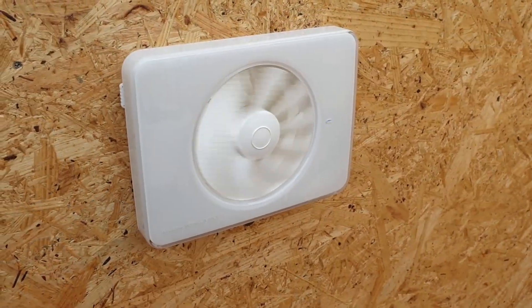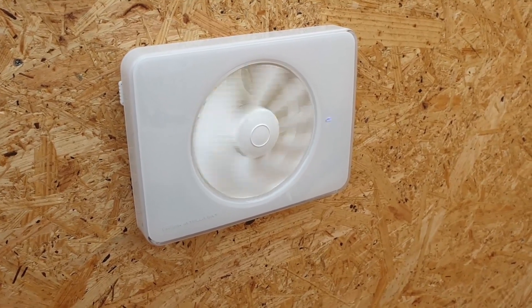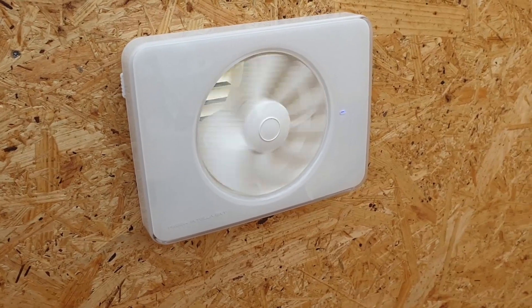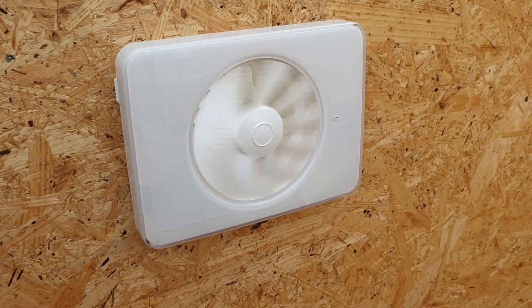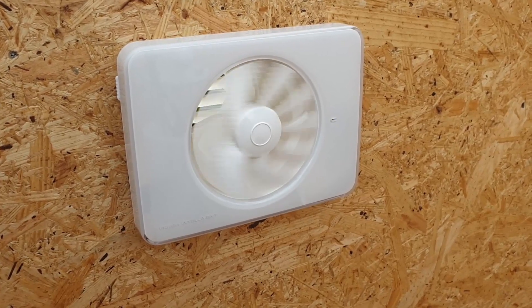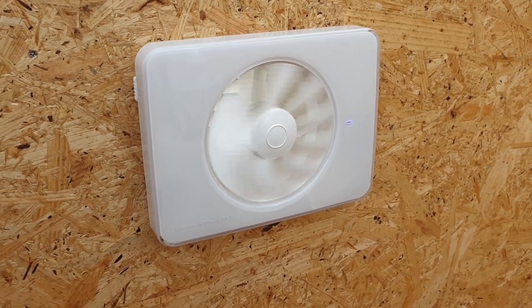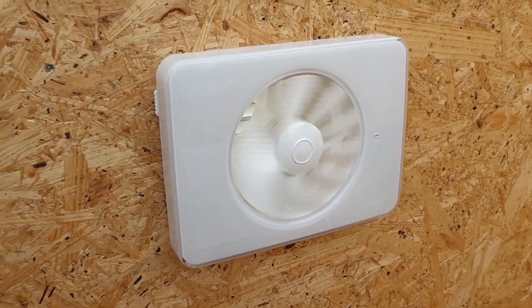The fan has been installed by an electrician and I have configured it. It's running through a ventilation mode — it does this once every 24 hours. The normal operation of the fan is to ventilate at a very low speed, and if the moisture rises above 70% relative humidity in the air, it will speed up to add ventilation to the observatory.